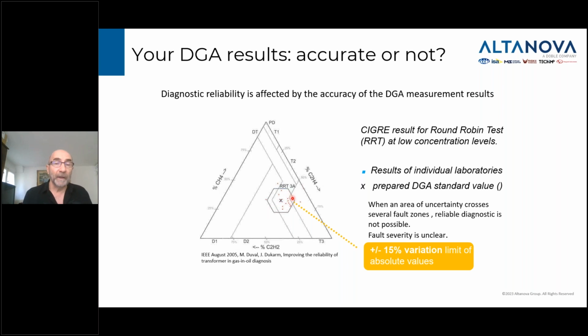So as the accuracy gets better from 15%, let's say, to around 5 to 6%, that surface shrinks significantly around the optimum diagnostic point. And what it means now is that the accuracy of that diagnostic increased significantly, and that's mostly what everyone is trying to get during a DGA.